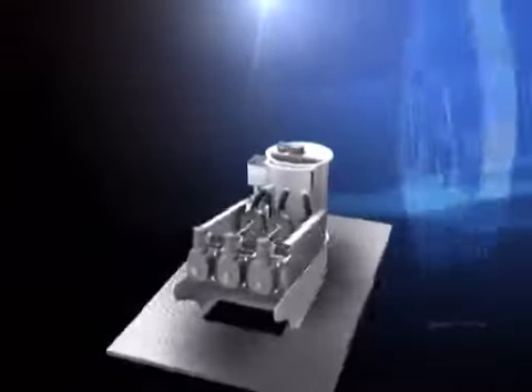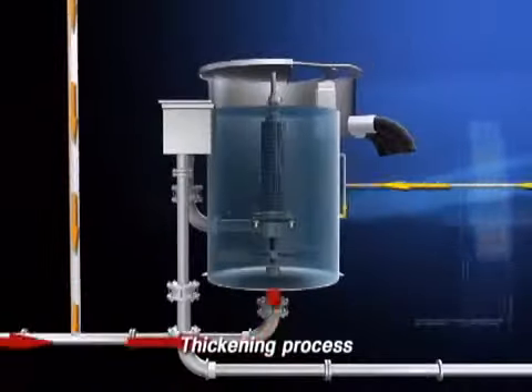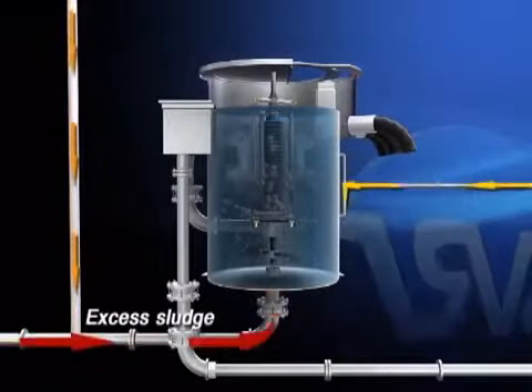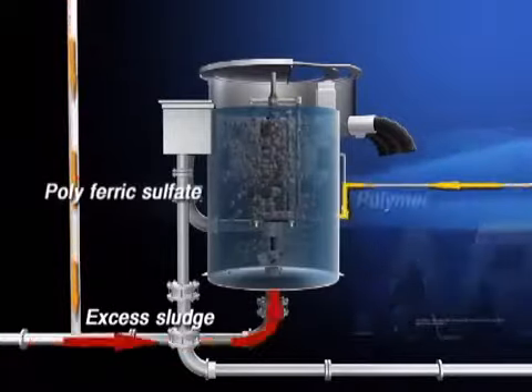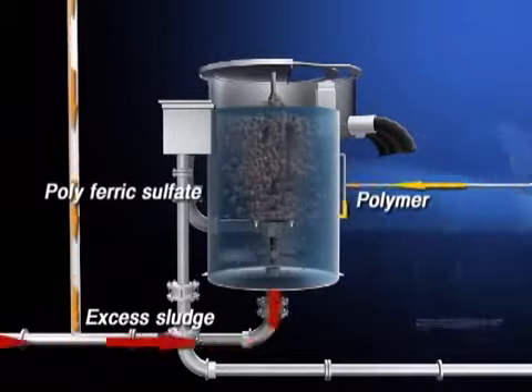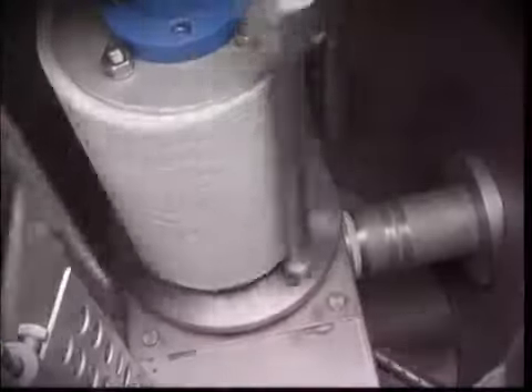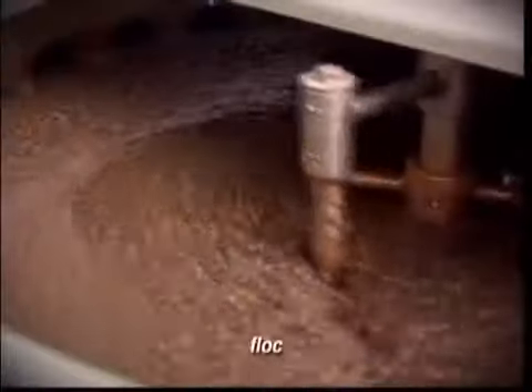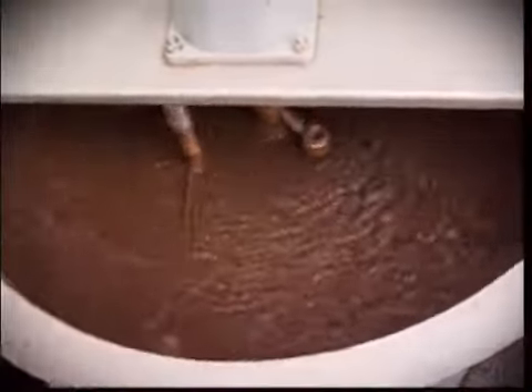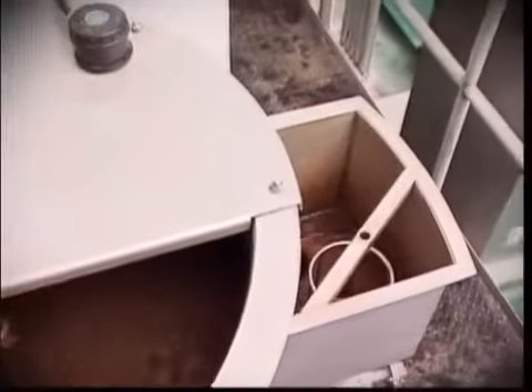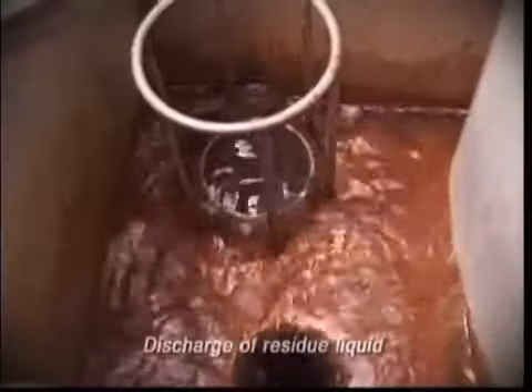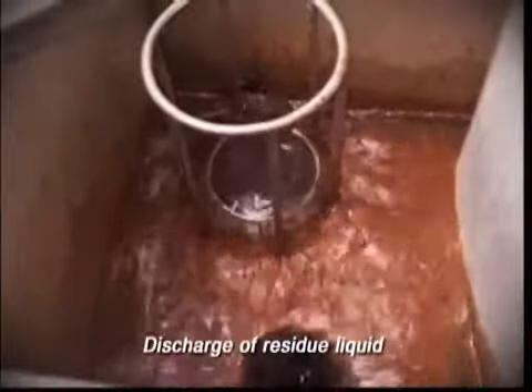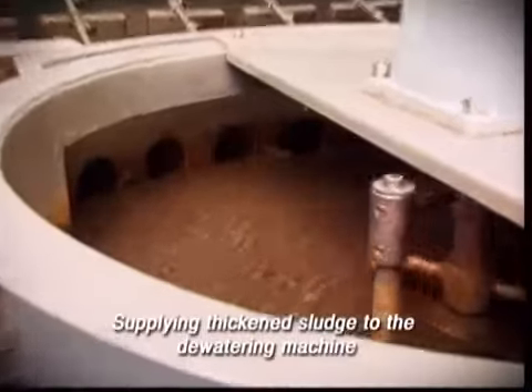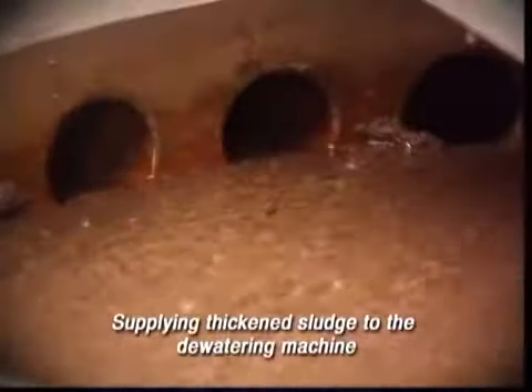Let's look at how our thickener and multiplex plate dewatering machine processes sludge. Sludge is first combined with polyferric sulfate and polymer to form flocks during the concentrating process. The flock is concentrated as residual liquid is separated from the sludge by the residue discharge device. The residual liquid returned to the early treatment plant, and the thickened sludge is brought to the dewatering machine.